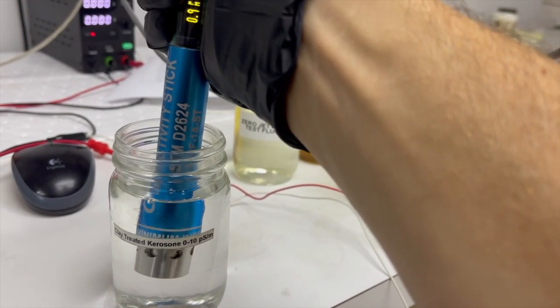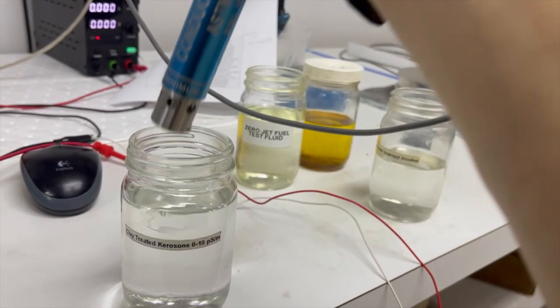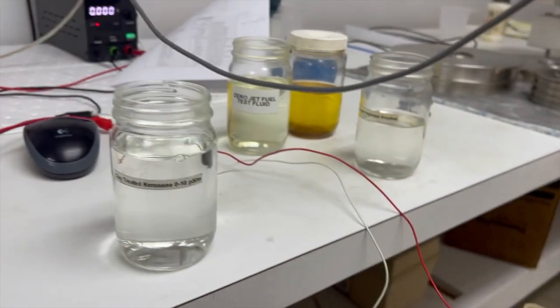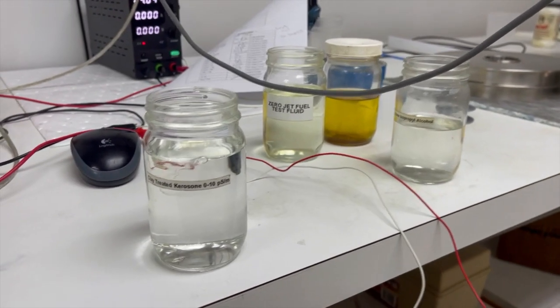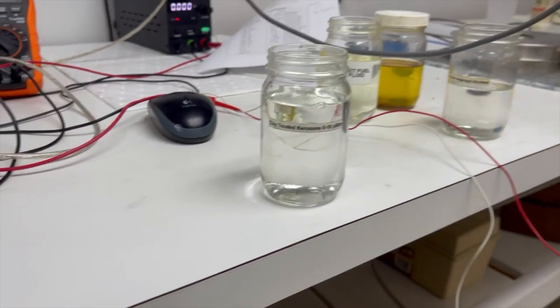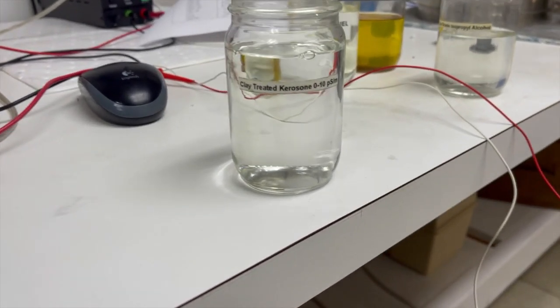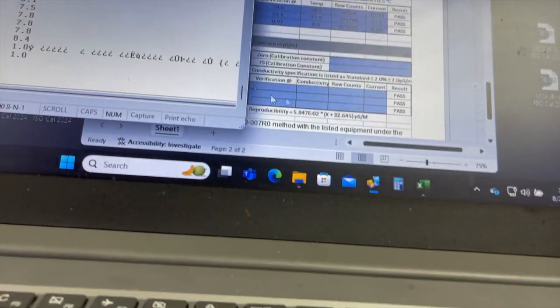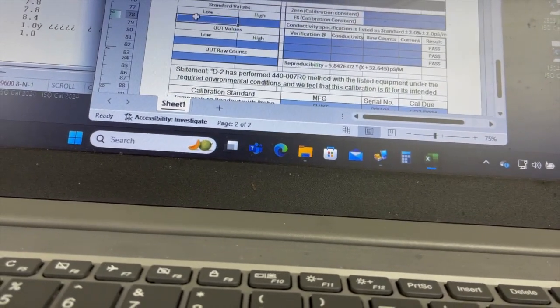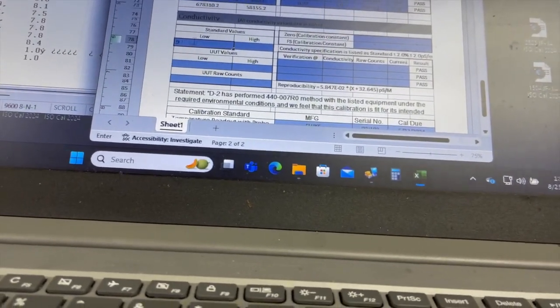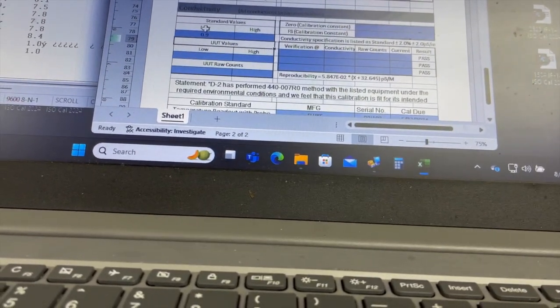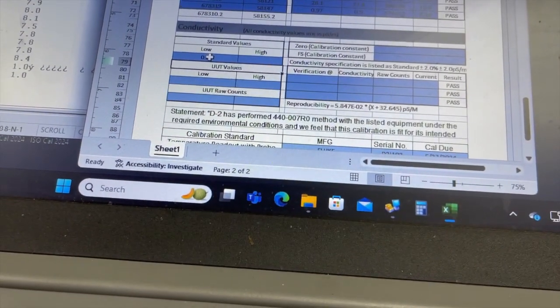We have 0.9 for a reference measurement. So very clean fuel, 0.9 picosiemens per meter. We're going to go ahead and use that. Generally I take 3 measurements, but because this is a video, we're going to do 1. But generally you take 3 and then you take the average of the 3 and use that as your reference.